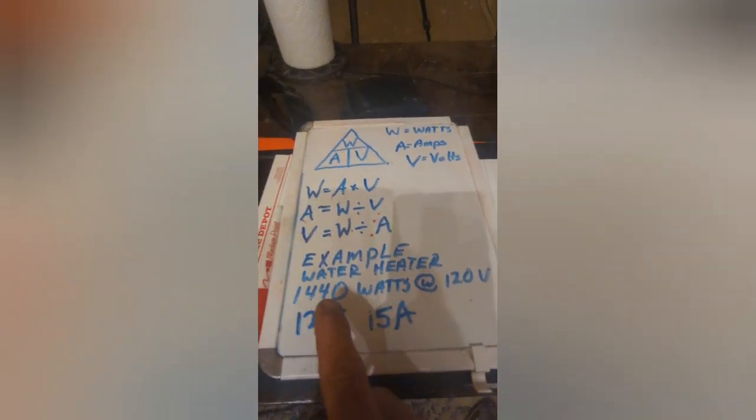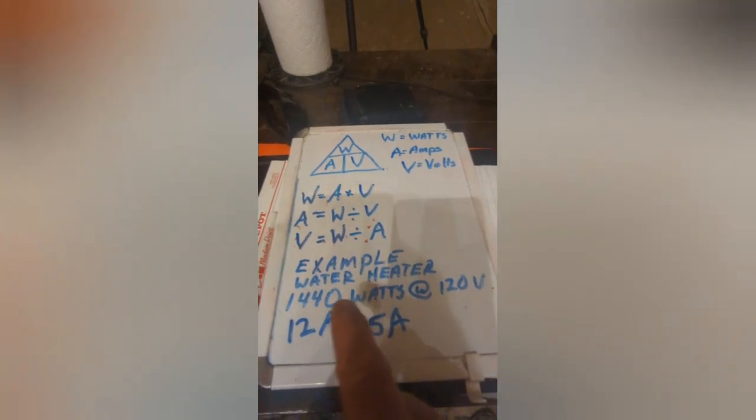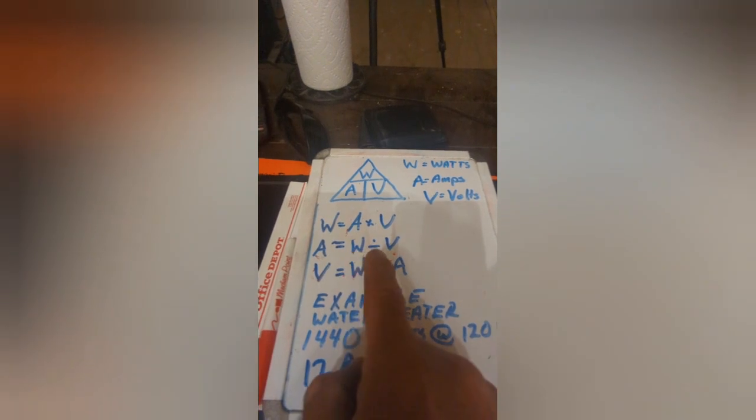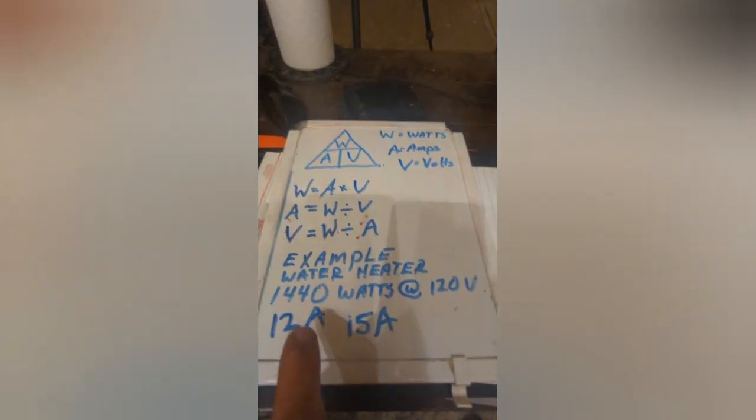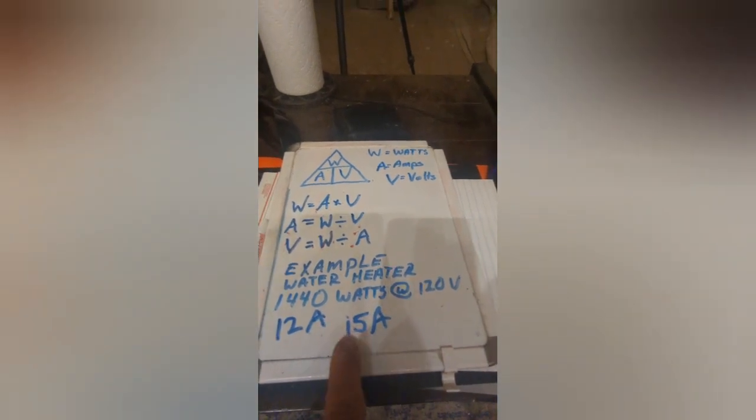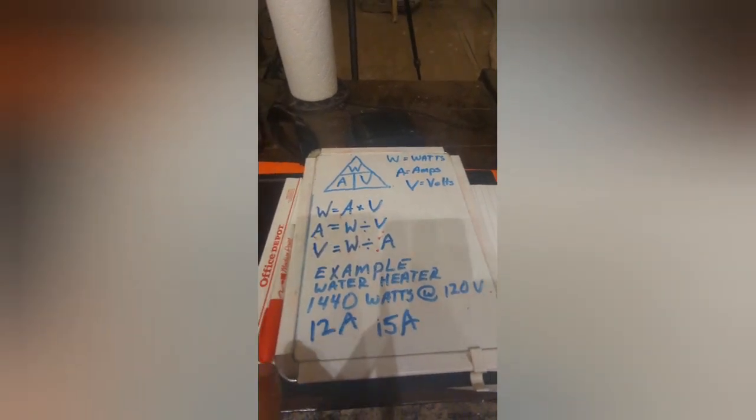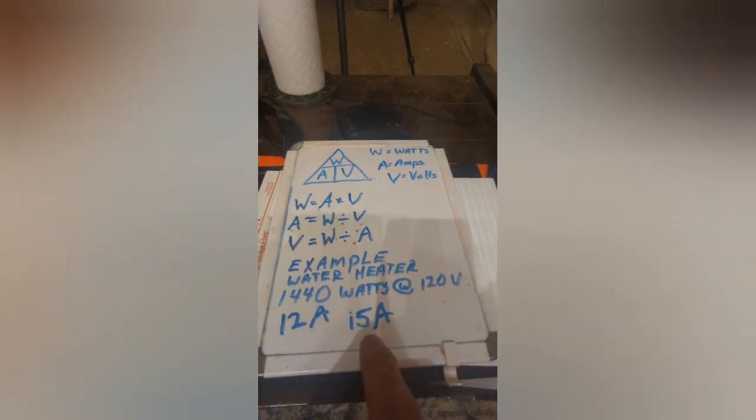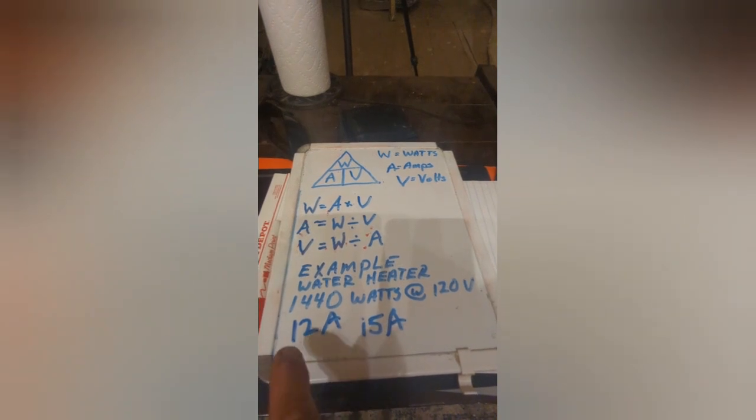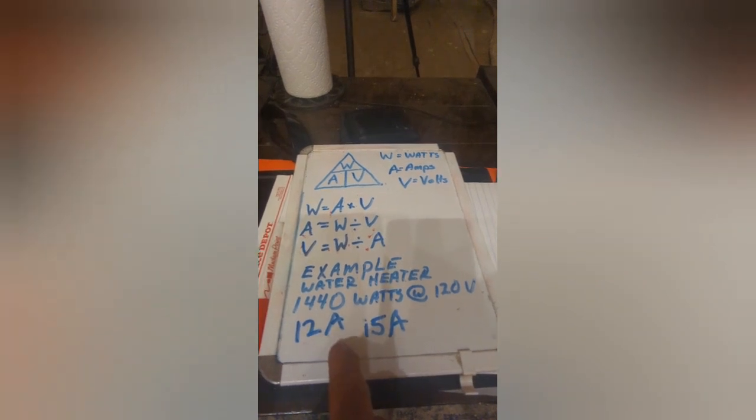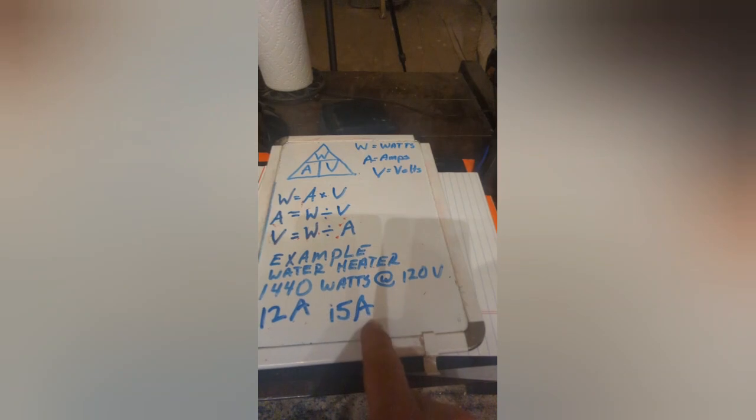So all I got to do is punch this into my formula here and say, okay, I need to know amperage. So I look here, I need wattage divided by volts. That gives me 12 amps. Now in order to size my breaker, we go back to that 80% rule. Now what I'm going to do here is I'm going to divide this by 0.80 and that's going to give me 15 amps.